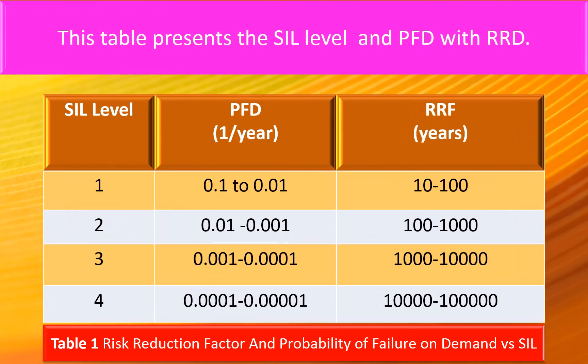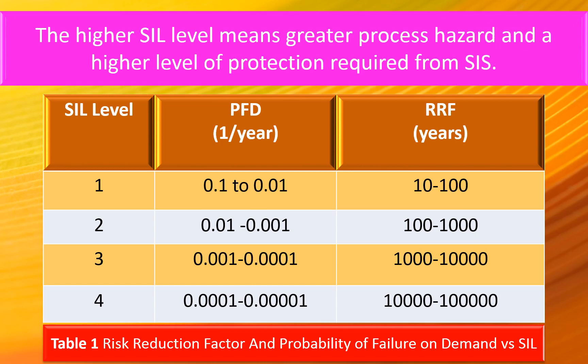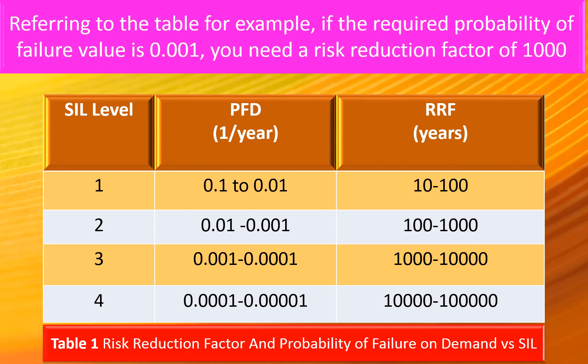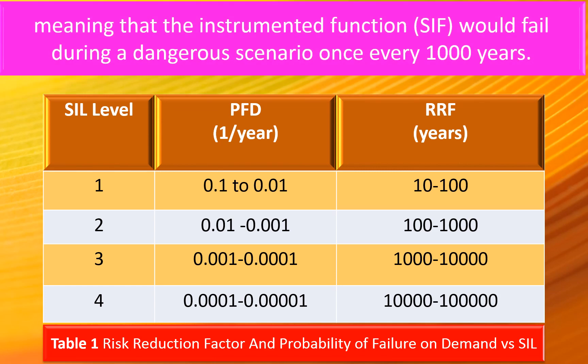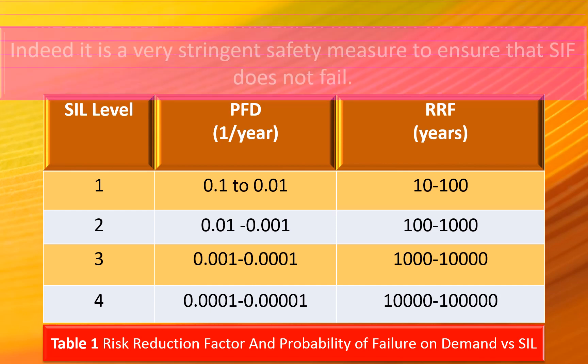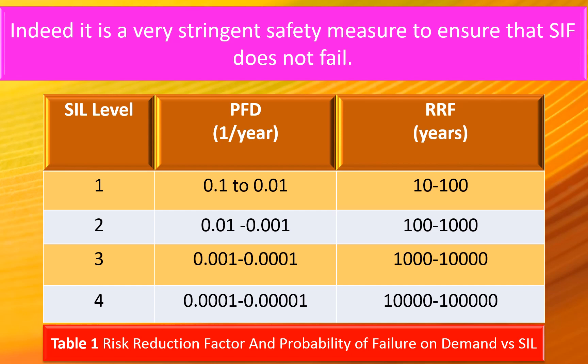The table presents the SIL level, the PFD, and the RRF. A higher SIL level means greater process hazard and a higher level of protection required from SIS. For example, if the required probability of failure value is 0.001 per year, you need a Risk Reduction Factor of 1000 — meaning that the Safety Instrumented Function would fail during a dangerous scenario once every 1000 years. This is a risk reduction measure to ensure that the SIF does not fail.